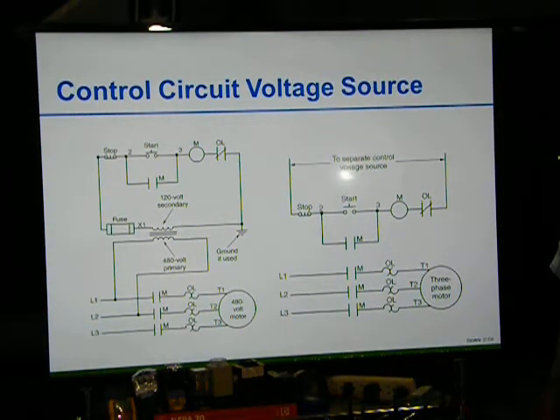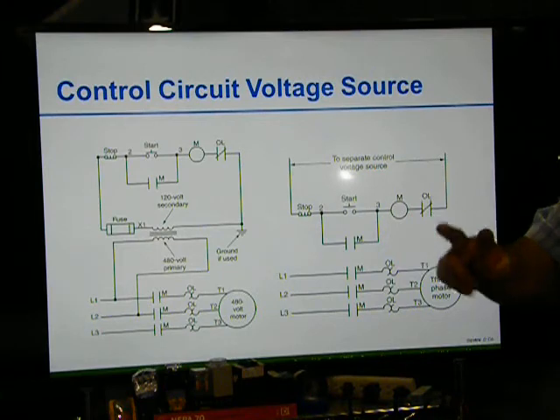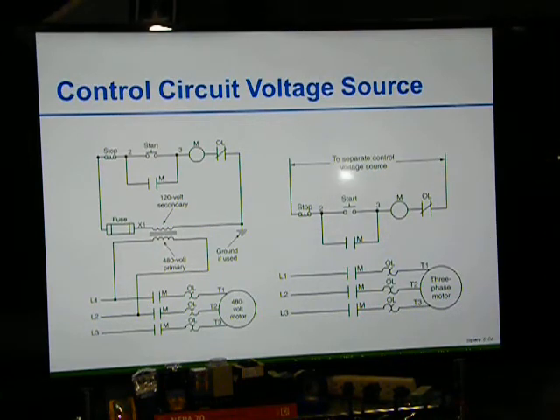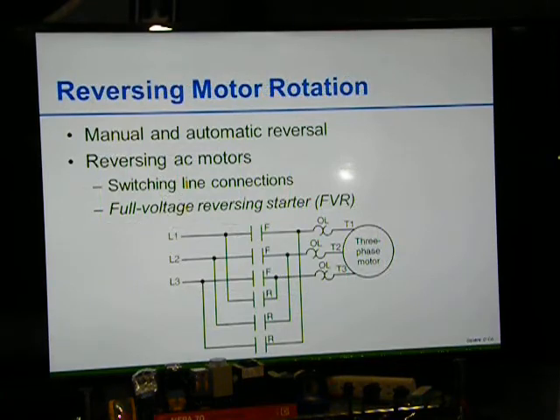But on a transformer it's more important, because the thing had about 10 to 15 motors. If the rotation was wrong, so we had to switch two wires, guess what? All those motors on there might have turned in reverse. Now we have to go back and change them out. It's easier just to do it at the transformer. So changing rotations, checking rotations, it's always a nice thing to do.